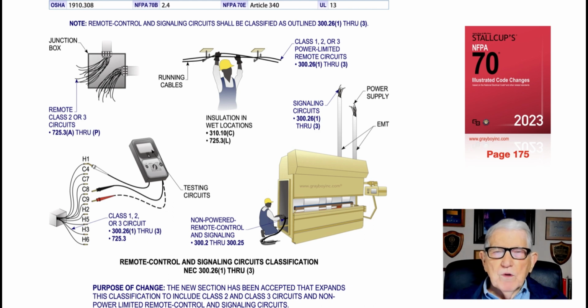But to get the 120 volt, 208 volt, 240 volt, or 480 volt control that we are used to dealing with, we have to go to chapters 1 through 4 and pick up the respective voltage. And those voltages are mentioned in 220.5 as well as other articles, what would be the normal voltage. Also in Article 100 they're defined. So keep that in mind, and that's what this illustration is illustrating to the user of the NEC, the separation of a Class 1 circuit from Article 725, which will deal with Class 2 and 3, and provide an article of its own for Class 1 circuits, which would be Article 724.